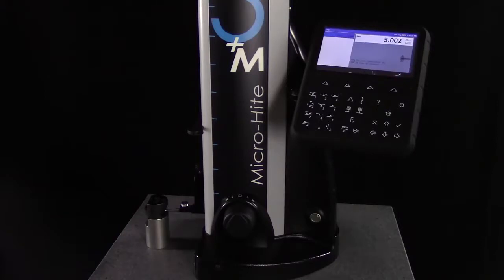Once the gauge is calibrated, you're ready to establish your datum point and begin measuring. I'll set my datum to the surface plate by turning the rotary control handle counterclockwise and moving the probe downward.